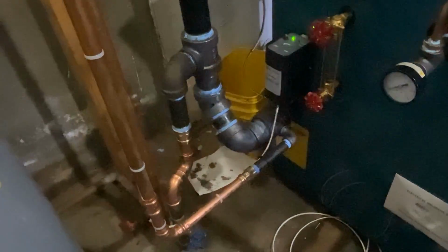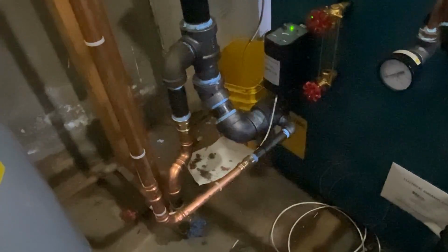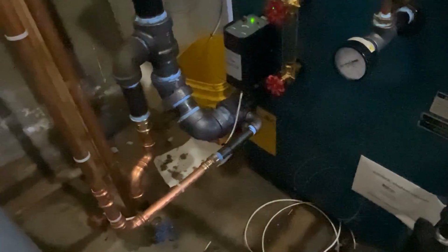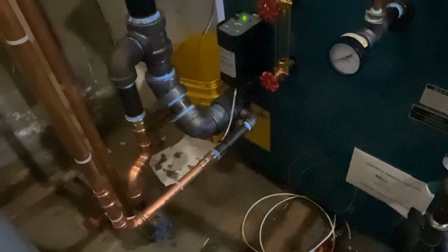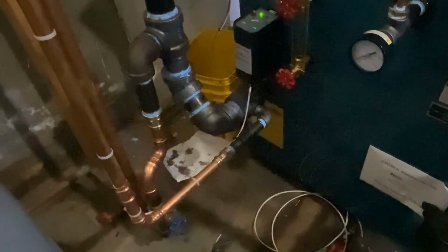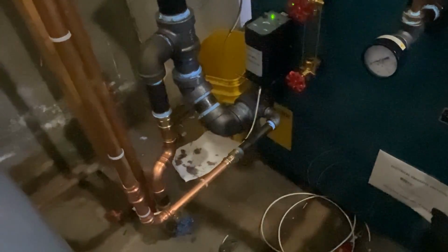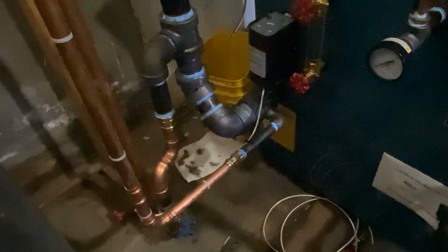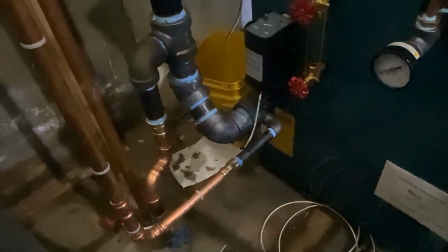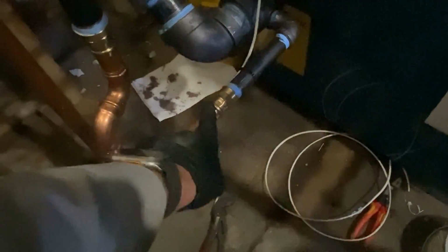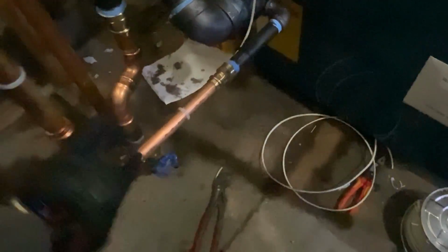Our piping out of the left-hand bottom side of the boiler, we came out with a 2-inch black nipple, followed by a 2 by 3/4 steam T. The 3/4 side is picking up our water feed. So here we use a 3/4 inch black 90, a nipple, a Viega brass female adapter, that's our dielectric connection, and of course our water supply.